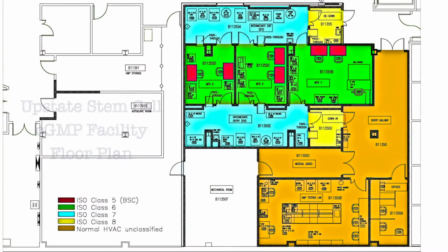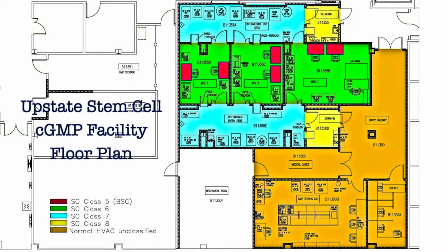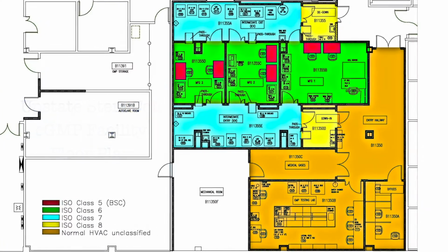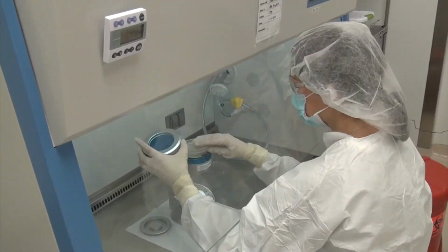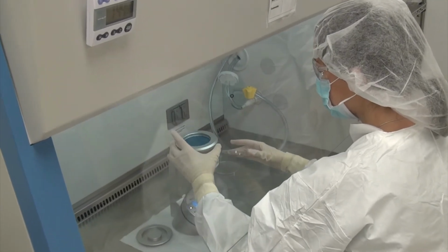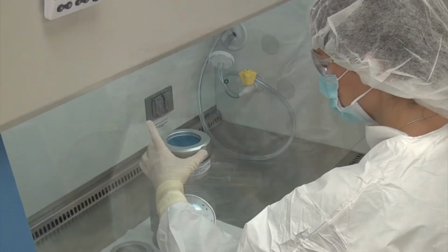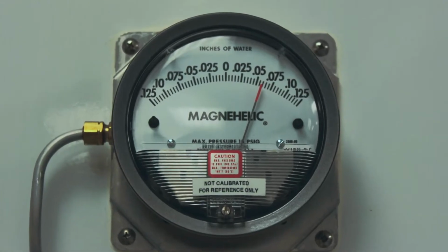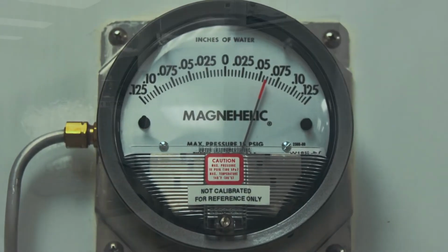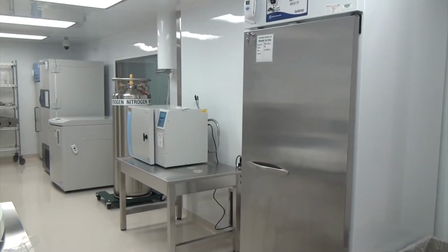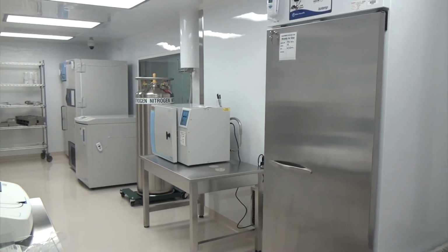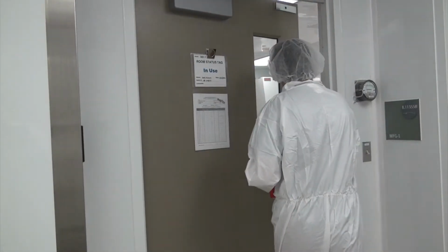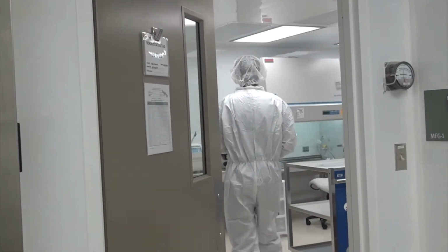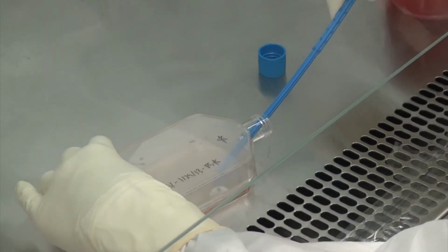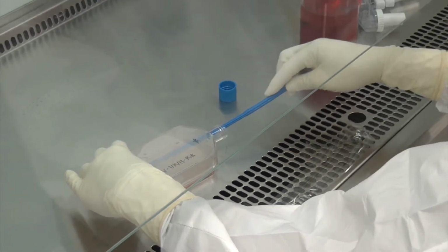The controlled manufacturing environments include HEPA-filtered air from redundant air handling units, providing clean room air quality from ISO Class 8 to ISO Class 5. Minimum pressure differentials of 0.05 inches of water column are maintained between adjacent clean rooms as well as between clean rooms and outside uncontrolled environments. In addition, room temperature and relative humidity are controlled to meet rigorously defined specifications.